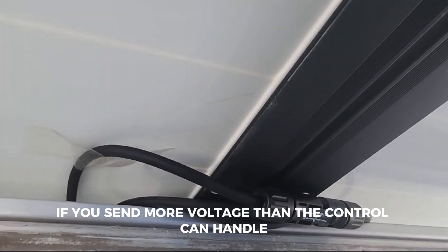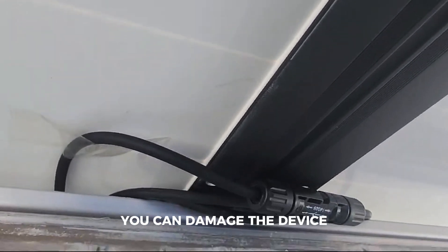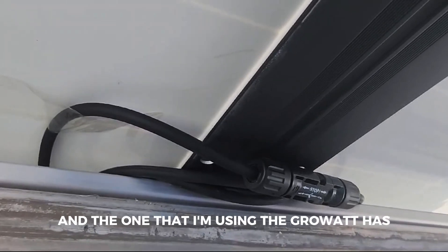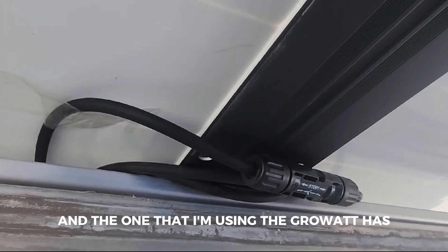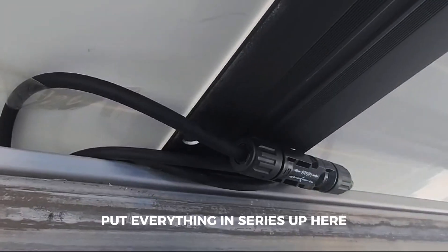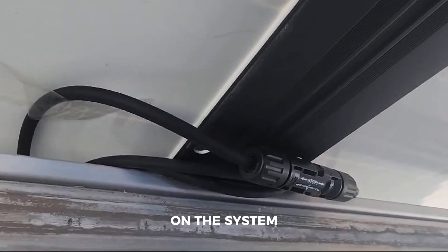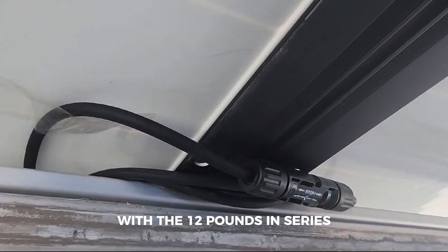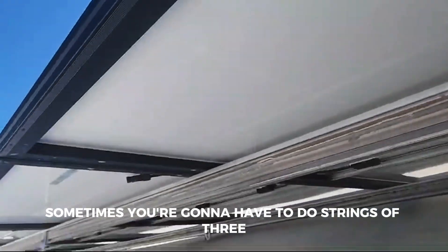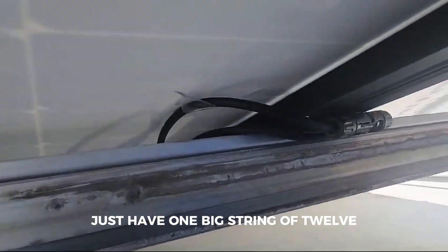Keep in mind the voltages of your charge controller or your inverter, because if you send more voltage than the controller can handle, you can damage the device. Some devices are as low as 150 volts max. The one that I'm using — the Growatt — has a max input of 500 volts. That's why I can put everything in series up here, because I'm not gonna reach 500 volts with 12 panels in series. Sometimes you're gonna have to do strings of three; sometimes you can just have one big string of 12.